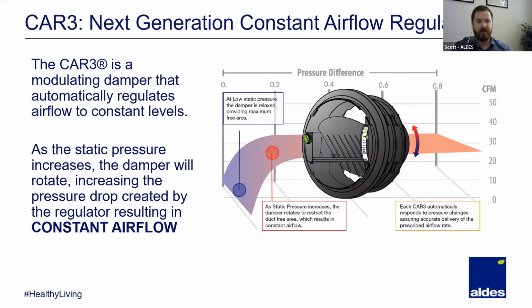So how does the CAR3 work? The CAR3 is a modulating damper, and what that means is it's a damper where you modulate how much free area you have. It works just like any other balancing damper, the difference being that it creates however much pressure drop is necessary to maintain a certain airflow. And I have one here, and hopefully people can see it through my white background. As I have an increase in pressure, I'm going to have an increase in velocity, and this damper is going to rotate. And so this device is going to create more pressure drop than it does in the relaxed position. Basically, this movement here is the airflow regulator moving through its operating range.